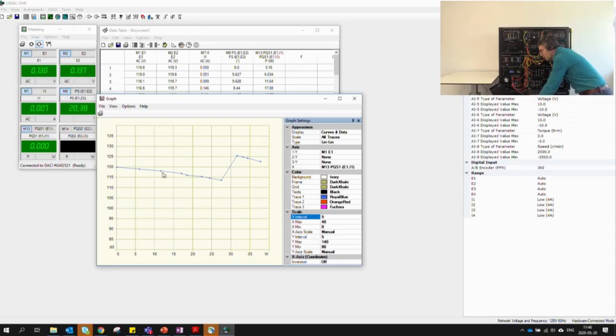So we started at 120, went down to 115, 114 when we decided to remove the compensating inductor, jumping back up to 125 and then dropping again. Of course, this is much too crude a control for a real power grid, but the goal is to show that with inductors in parallel with our loads, we are able to achieve compensation. The next step, as done in the manual, is to take a bank of inductors and a bank of capacitors working in parallel to achieve much finer control, switching them in and out at the right moment to maintain the voltage at the receiving end within 1 volt of the expected 120 volts, or 220 volts if you are outside North America.